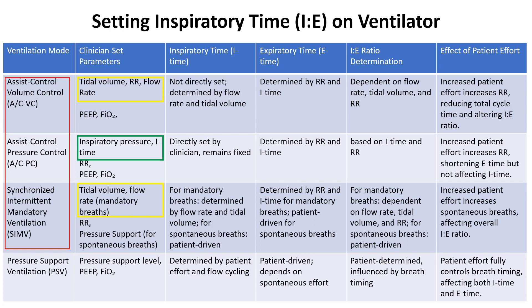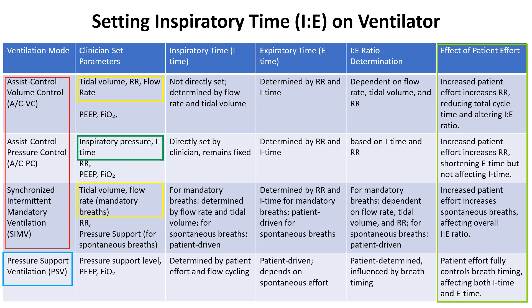The main difference comes from patient-triggered breaths, which can alter the overall respiratory rate. In spontaneous modes like pressure support ventilation, there are no set mandatory breaths, so inspiratory time and expiratory time are entirely dependent on the patient's effort, making the inspiratory-to-expiratory ratio variable.